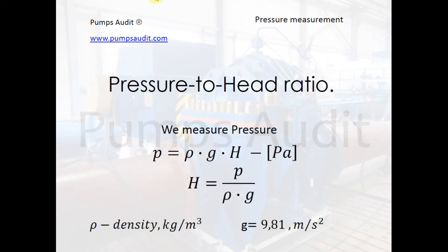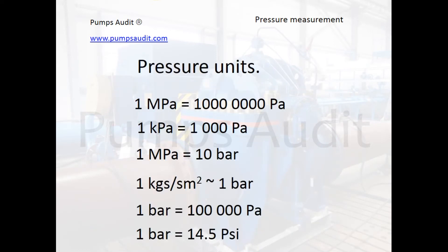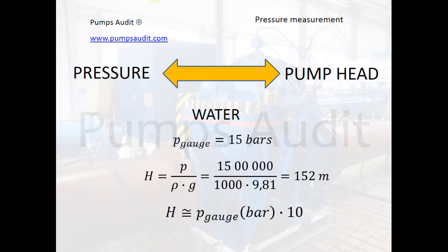The pressure-to-head ratio is worth keeping in mind every time we measure a pressure. This formula shows that pressure is equal to head multiplied by density and gravitational acceleration. On the other hand, head is the pressure divided by gravitational acceleration and density. These are the most popular units of pressure we use and ratios between some of them. For approximate evaluation of pump head using pressure measurements, a simplified ratio can be used. For example, for cold water, head is equal to pressure in bars multiplied by 10.